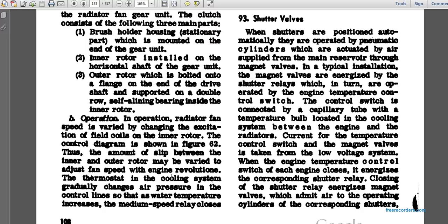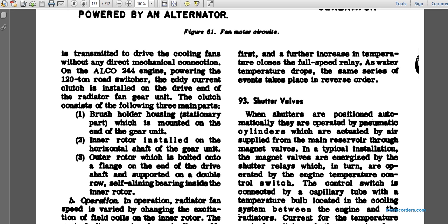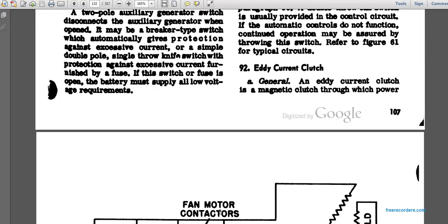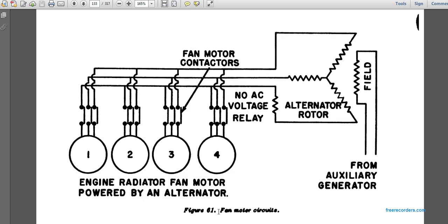The amount of slip between the inner and outer rotor may be varied to adjust fan speed. As engine temperature increases, air pressure builds in the control lines. As water temperature increases, the medium speed relay closes first; further increase causes the full speed relay to close. When water temperature drops, the same series of events takes place in reverse order.